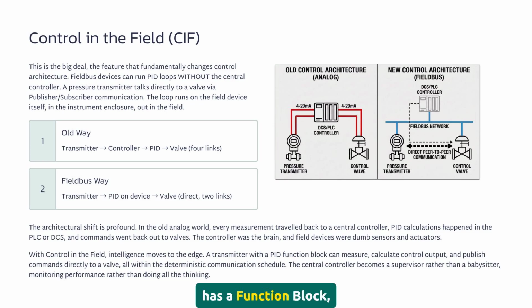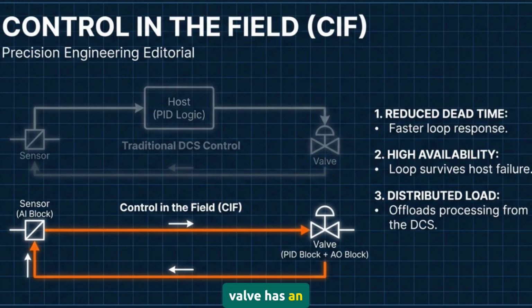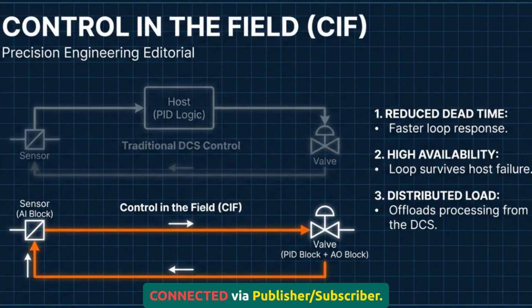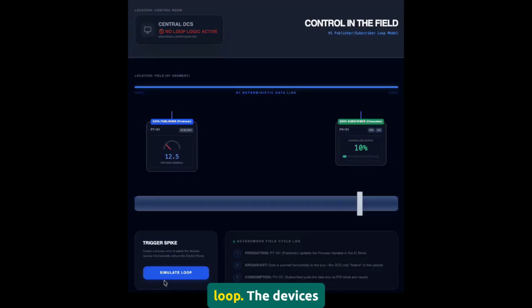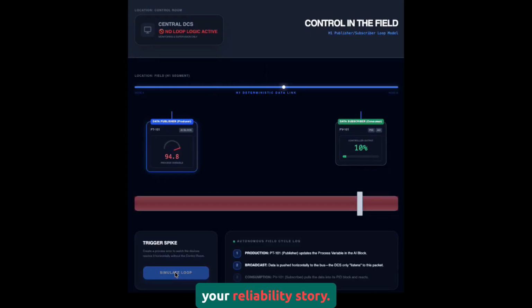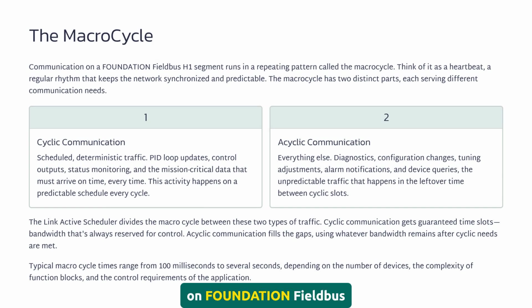The transmitter has a function block, an AI block, analog input. The control valve has an AO block, analog output. They're directly connected via publisher-subscriber. The PID loop runs on the transmitter or on a field-mounted device. No central controller needed for that loop. The devices are thinking for themselves. That changes your reliability story. Central controller goes down, your backup protection's still running, your critical loops keep working, you don't lose everything. Now the communication on Foundation Fieldbus happens in what's called a macro cycle.